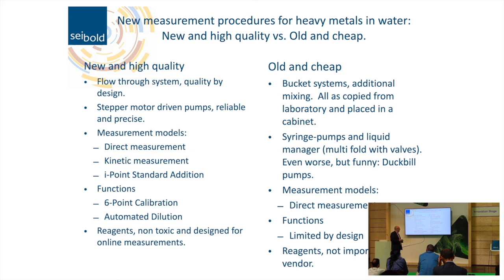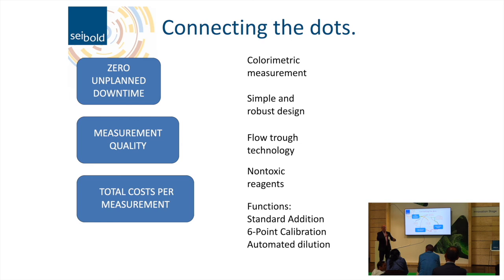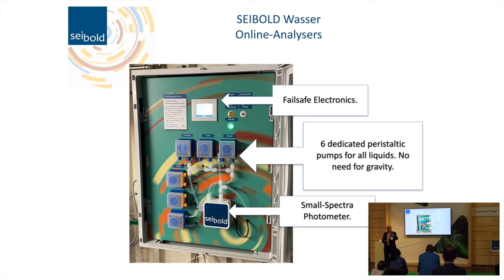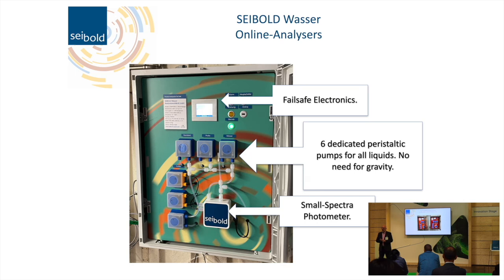Now, connecting the dots: we have discussed the three main criteria — zero unplanned downtime, measurement quality, and total cost per measurement. We have colorimetric measurement, the flow-through technology, and a simple and robust design. The analyzer consists of three parts: failsafe electronics, six dedicated peristaltic pumps for all liquids (no need for gravity), and a small spectrophotometer. It's a simple setup — you check if there is power, if pumps are turning, and if the photometer gives light. Everyone can easily verify if the analyzer is measuring correctly.